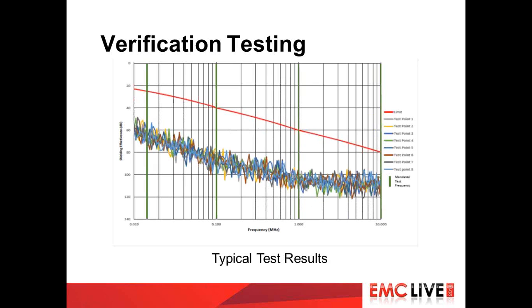This is an example of an overlay of 8 various points that might have been tested on a shielded enclosure. The red line is showing the limits of the 188-125, and the other lines are showing actual measurements from the 8 points that were measured on the shielded enclosure. As you can see, it's well within the limits, and this would be a very successful shielded enclosure for EMP applications.